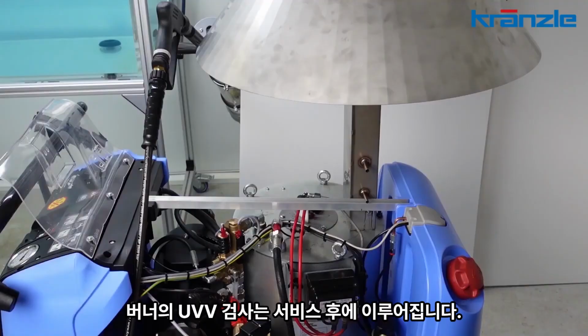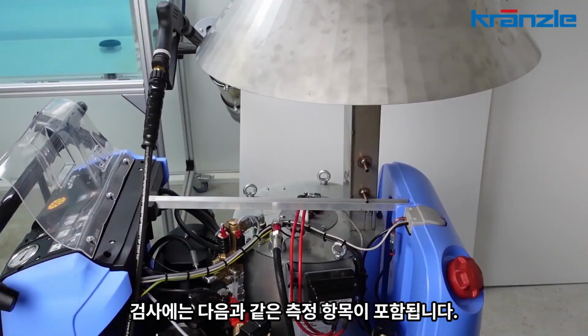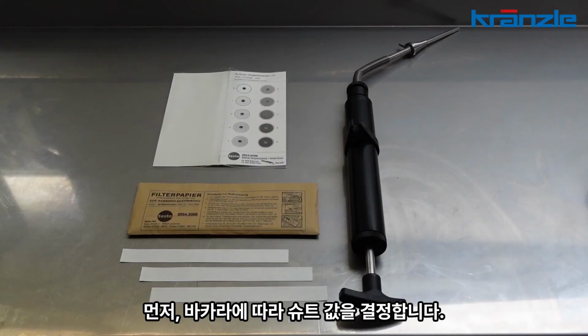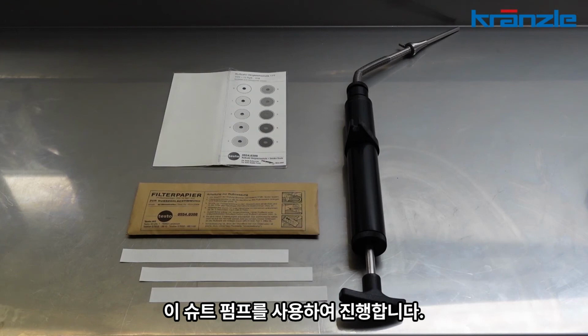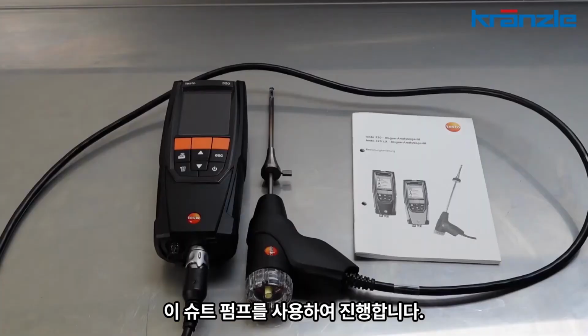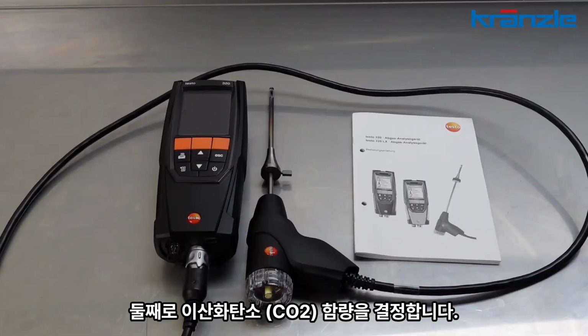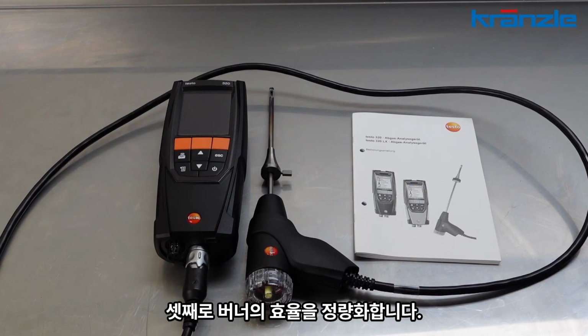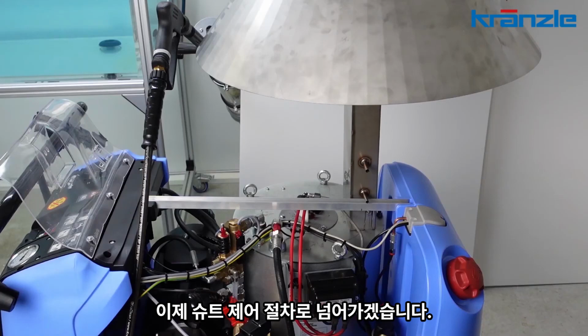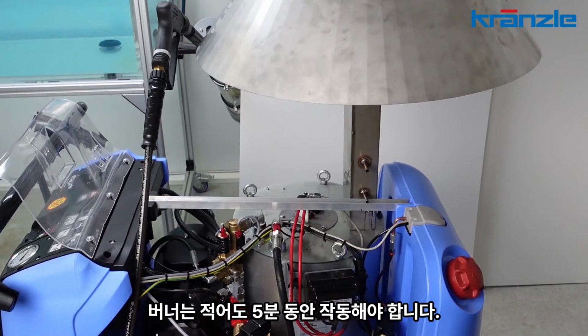The UVV inspection of the burner after a service includes the following measurements. First, determine soot value according to Bacharach with this soot pump. Secondly, determine the CO2 content. Thirdly, quantify the efficiency of the burner. Now to the procedure for the soot control. The burner must be in operation for at least 5 minutes.